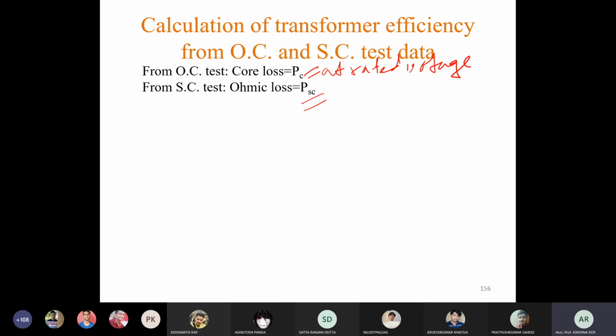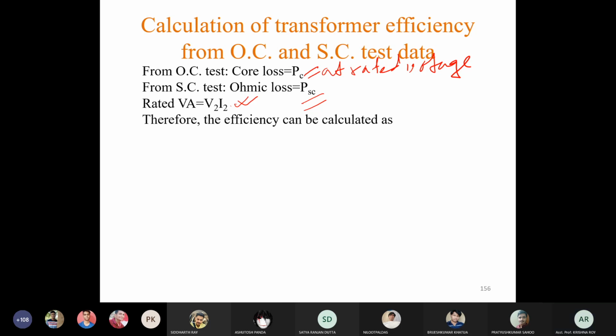Okay, that's what I was telling in the previous problem. So PSC you have to check. Rated VA, that is V2 I2, is the nameplate data. Okay, you will get it from the nameplate of the transformer. So therefore the efficiency can be calculated using the formula.